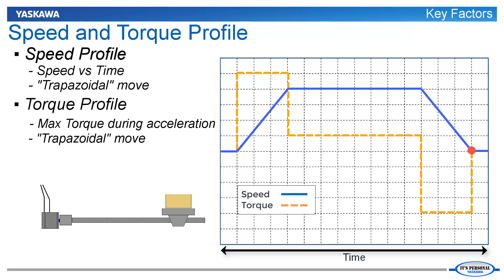Due to its shape, this is referred to as a trapezoidal speed profile, or a trapezoidal move. The torque at the beginning of the trapezoidal move is highest because mechanical friction must be overcome and because the load must be accelerated from rest. This point of highest torque is called the max torque.